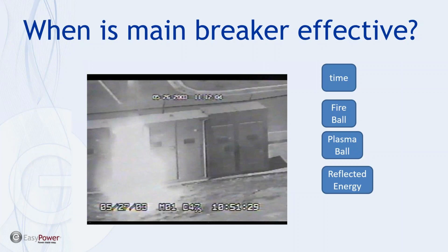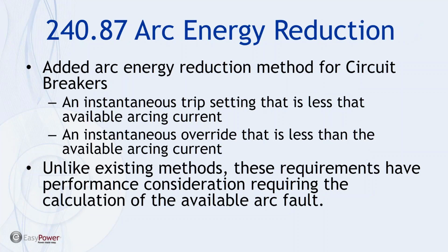So the question I have of my data collection folks is, if that plasma ball is located in the area of the main breaker, will the main breaker do its job? So I repeat, this plastic barrier, does it really improve the arc flash situation? And again, I direct that question to the people doing data collection, because they're the ones that have to make this assertion about the main breaker should be included or excluded. Okay, so this alone doesn't make anything official about arc flash.